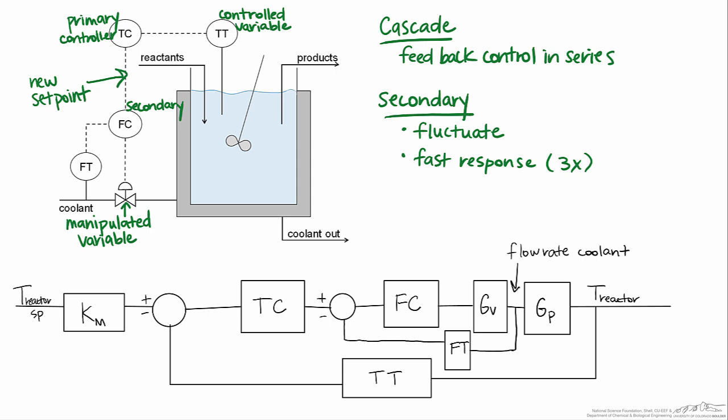Generally when tuning you tune from the inside out, so therefore in this case we would tune by starting with the secondary loop, then the primary loop. So for the sake of what we're talking about here this would be the flow loop first, then the temperature loop. The stability of the process can be greatly influenced by how the secondary flow loop has been tuned.